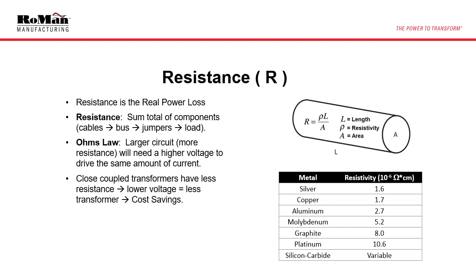Resistance is a relatively simple concept. Resistance comes from the sum total of components, including cables, busbar, jumpers, and load. Ohm's law tells us that a larger circuit will require more voltage for the same amount of current. Efforts taken to reduce resistance outside of the heating element will allow us to drive more current at a lower voltage. This is a consideration when designing busbar dimensions and material types. Additionally, Roman's smaller water-cooled transformers allow us to get closer to the process and thereby reduce resistance. This correlates to lower voltages, less transformer, and cost savings.